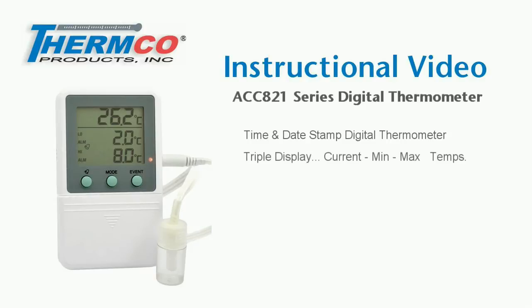The 821 has a triple digit display that simultaneously shows the current, min, and max temperatures. The unit has a temperature range of minus 50 to 70 degrees Celsius, minus 58 to 158 degrees Fahrenheit, with an accuracy of plus or minus 0.3 degrees C, plus or minus 0.5 degrees Fahrenheit.